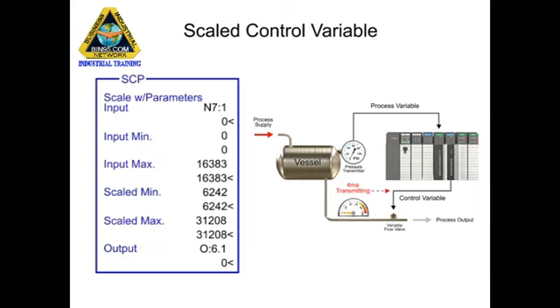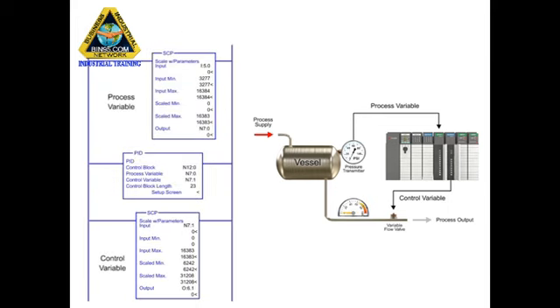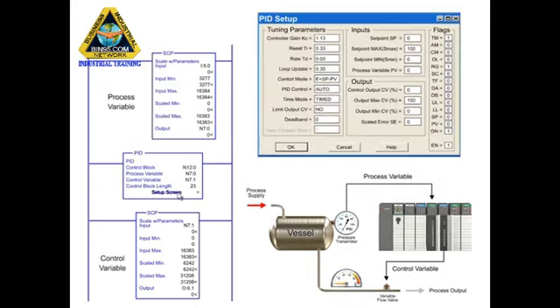The analog signal is then sent to the flow valve where the operating range is adjusted between 0 and 100%. With the data scaled using the SCP instruction, the process of controlling the pressure of the vessel to 50 psi continues by entering the setpoint of 50 in the PID setup menu.